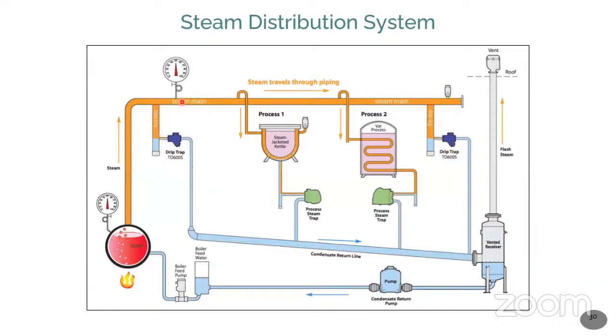You see the brown color is the steam line, and the blue color is the water line. Okay, now the condensate water will be available here, and that can be connected to your receiver, your tank. Okay, the condensate collection tank. From that you can again take the water with the help of a high speed, high temperature pump to your feed water tank, because this feed water will be given as an input to the boiler. So if you properly collect all your condensate, then definitely your feed water temperature will be increased. That will reduce your fuel consumption, right?